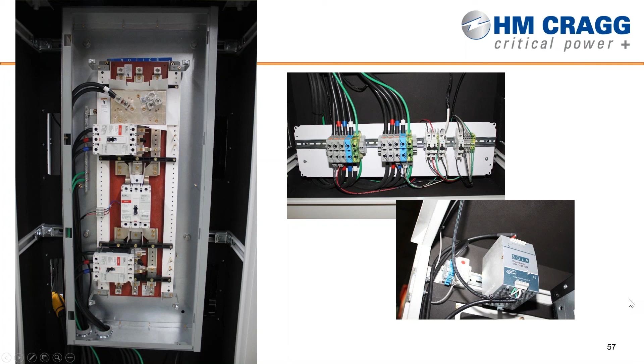We utilize the tap offs from those sections to power up our critical devices, the hydrogen sensor, the emergency vent kit. And then on the input side, the utility side, we're running our air conditioner as to not utilize any of the capacity of the UPS. So minimum runtime allows us to do that. If there was an outage, it would be a minimal time where it's collecting heat in the enclosure. Once the UPS sees the utility back on, it'll start climate controlling again.